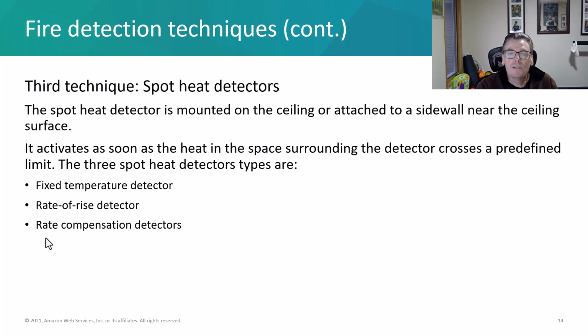The third technique is a spot heat detector. We can mount that on a ceiling or attach it to a sidewall up near the ceiling, and it can activate when the heat in that space crosses a predefined limit. There are three types of spot heat detectors. One can be a fixed temperature detector, which tells you that we've reached whatever that temperature may be, 180 degrees, 200 degrees, I'm not sure what it is. I'm just pulling those numbers out of thin air, but we're going to have a base number that says once we reach this number, kick it on.